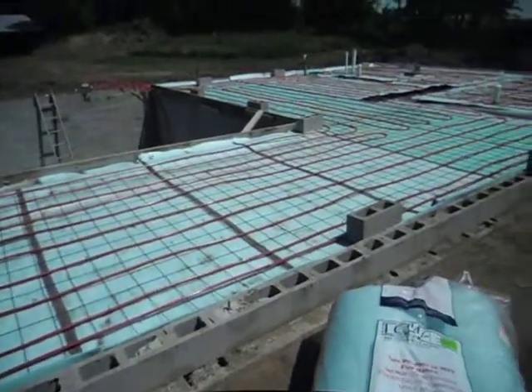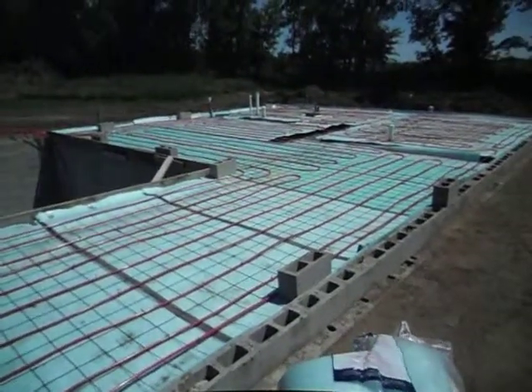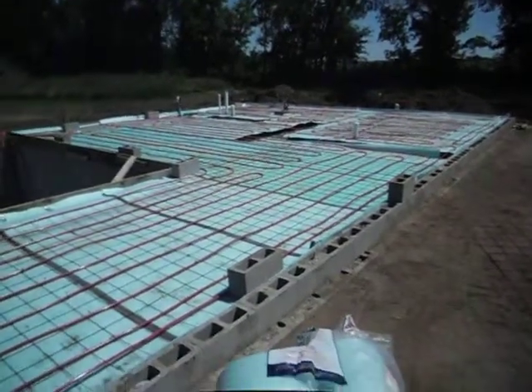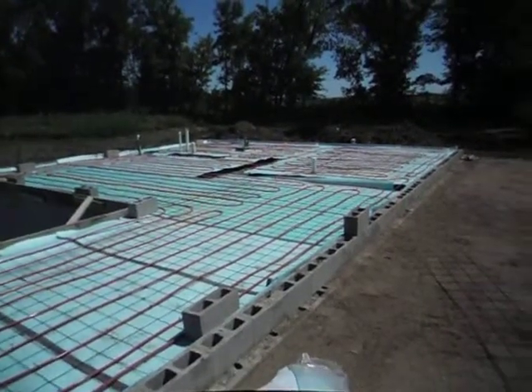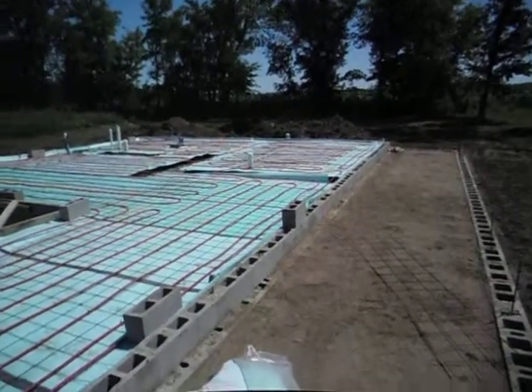We use PEX radiant floor tubing. The insulation of preference that we use is a Low-E brand reflective insulation called Slab Shield. It has a solid layer of aluminum inside of it, which gives us a 97% reflective rate back up to make the radiant floor highly more energy efficient than plain styrofoam.